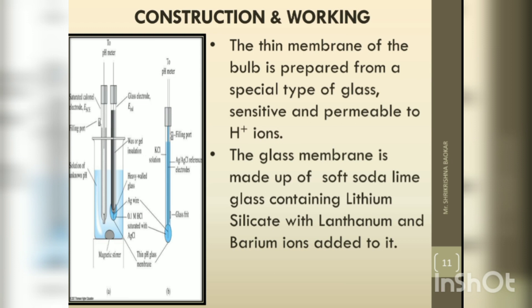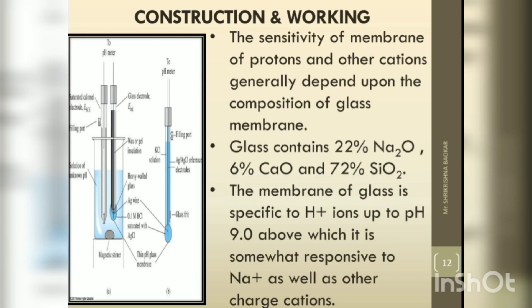The thin membrane of the bulb is prepared from a special type of glass which is sensitive and permeable to H+ ions. The glass membrane is made up of soft soda lime glass containing lithium silicate with lanthanum and barium ions. The sensitivity of the membrane to protons and other cations generally depends upon the composition of the glass membrane.